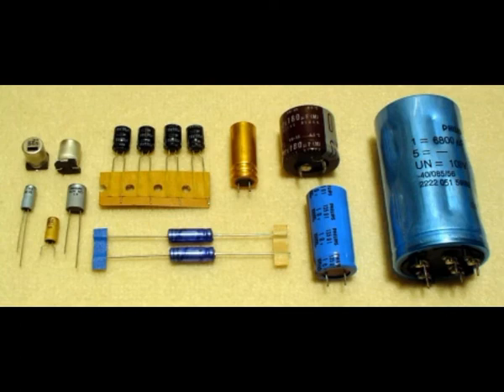Series connection. Some applications like AC converters with DC link for frequency controls in three-phase grids need higher voltages than electrolytic capacitors usually offer. For such applications, electrolytic capacitors can be connected in series for increased voltage withstanding capability.